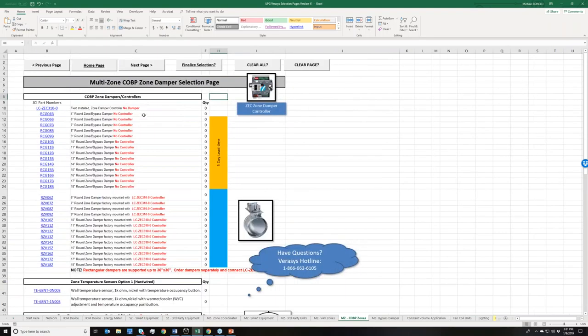Moving on to the next page, we get into zone dampers. As we started with this job, or specifically this rooftop unit, we said it was going to be changeover bypass, right? I could have a changeover bypass rooftop unit have nothing but VAV boxes if I wanted to. It has happened, doesn't happen a lot, but I could have VAV boxes on the job where the equipment has no drive and I still need a bypass.